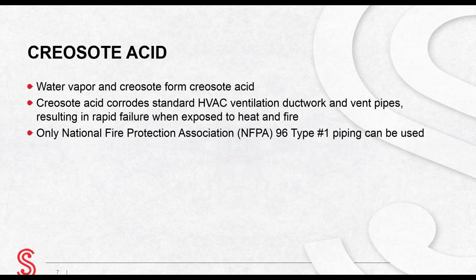Water vapor and creosote form creosote acid. This acid will corrode standard HVAC ventilation ductwork and vent pipes that are not NFPA 96 Type 1. NFPA 96 is the standard for ventilation control and fire protection of commercial cooking operations. The NFPA, National Fire Protection Association, creates standards and codes for usage and adoption by local governments.